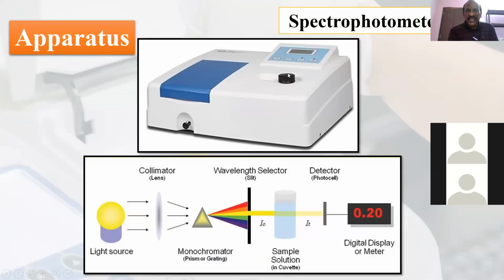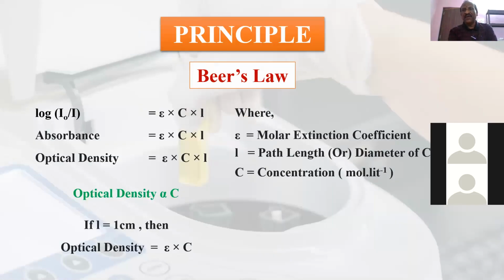Then if you rotate it, we get A, B, C like this. So the OD value, the optical density value, we can see here. If you rotate again, B will come and we get the B OD value. If you rotate, the C filter will come, and we get that value. If you rotate to D like this, with the cuvette filled with distilled water in this portion, we get a different filter, and that filter's OD we observe here. That value we can take in a tabular form.